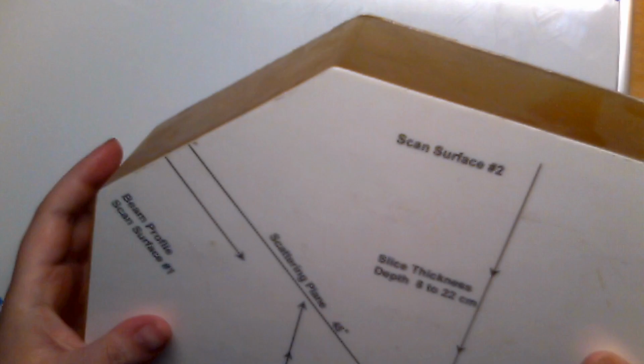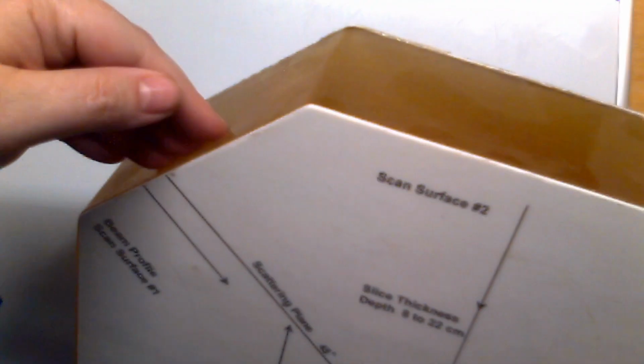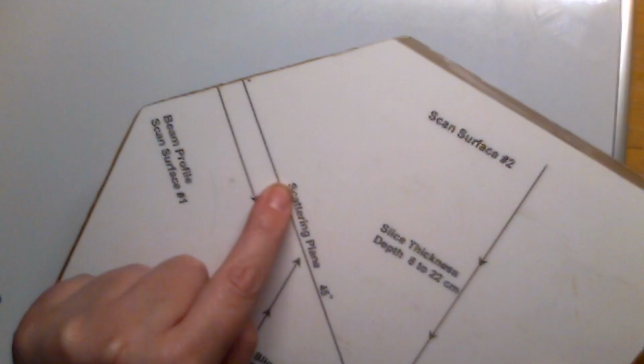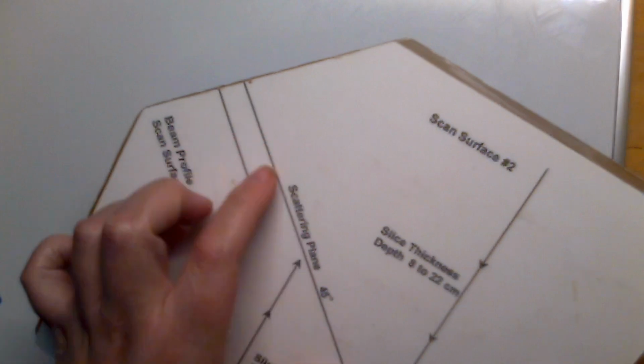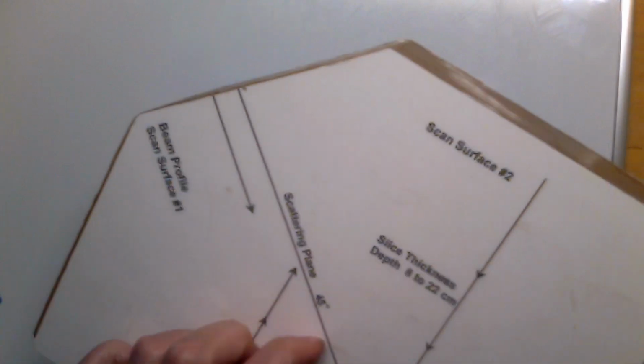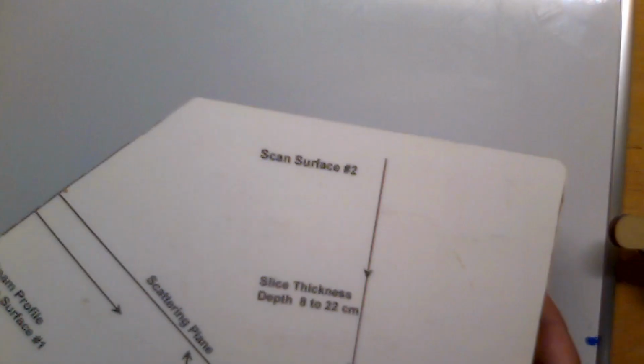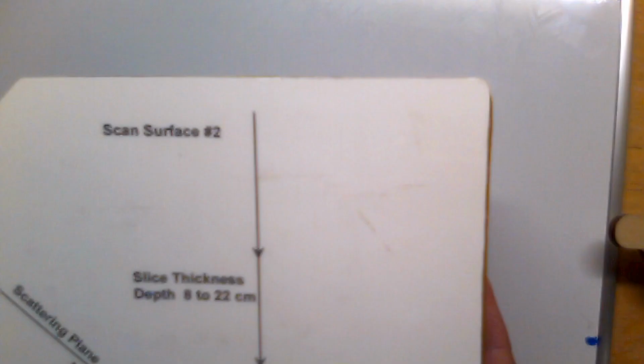We then come off to this angled side here, and we scan in through this part, and that's going to tell us where it is narrow, whether it narrows where our focus is set, and then we can see the beam divergence past the narrowing or past the focal point. So it's an interesting way to actually view the true thickness of the slice and of the lateral resolution as well.